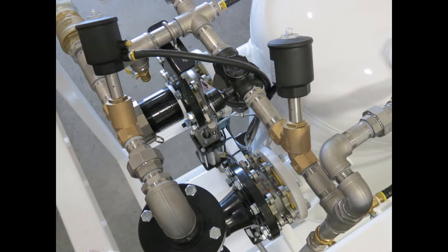The angle seat valve is a pilot operated pneumatic solenoid. When the pilot line is charged and it turns on the larger discharge angle seat valve, the pilot airline should be checked for wear and ensure that the connections are tight and there are no leaks.